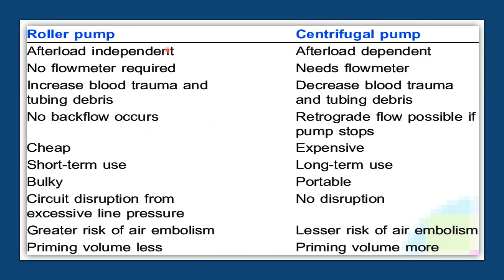Comparing roller pump and centrifugal pump: the roller pump is afterload independent, so circuit disruption occurs if there is excessive line pressure. It is an occlusive pump so no backflow occurs. Flow depends on revolutions per minute, so no flow meter is required. It is cheap and intended for short-term use.